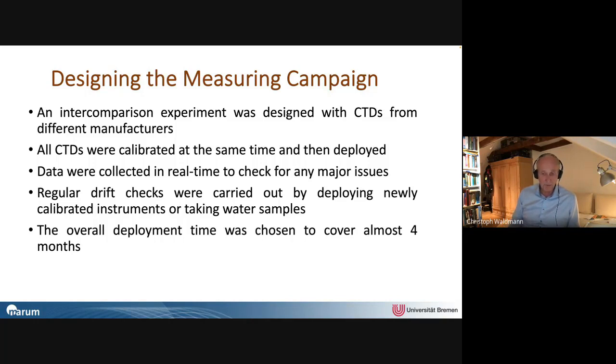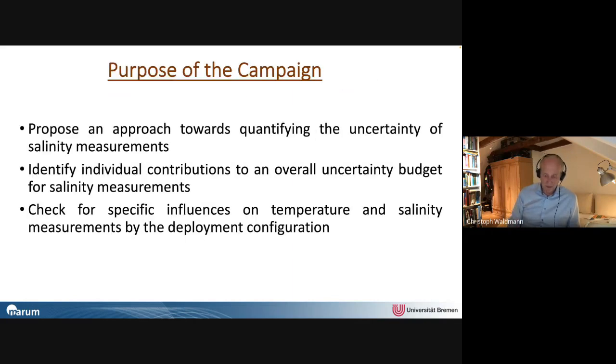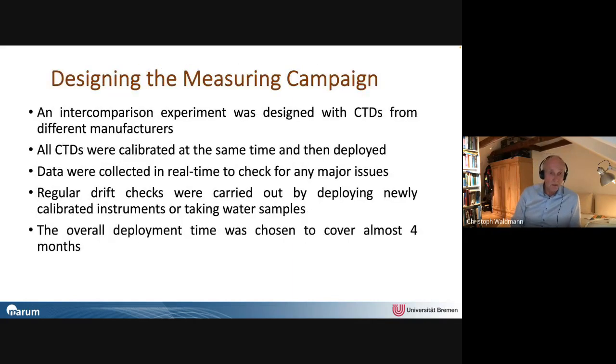I can give you a link to that publication later on. The basis was an intercomparison experiment with CTDs from different manufacturers. It was also important not just to focus on one specific instrument. We wanted to find out about the influence of the methods on the instruments. So all CTDs were calibrated at the same time and then deployed.